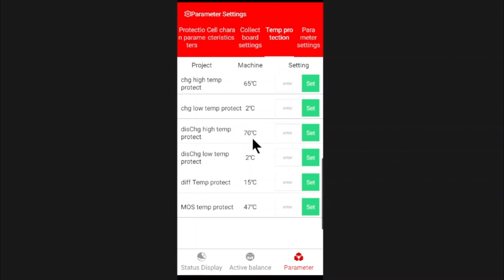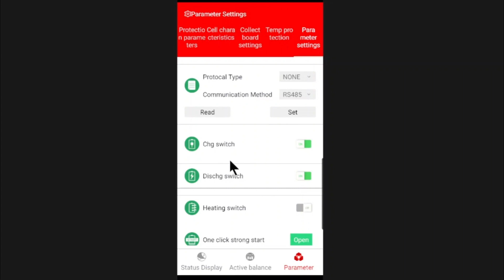For temperature, we need to make sure the low temperature cutoff is close to 0—I put 2 degrees Celsius, so charging will stop at 2 degrees Celsius. On the last page, you can actually switch things off—there are virtual switches to stop charging or discharging on the BMS, which is quite useful.